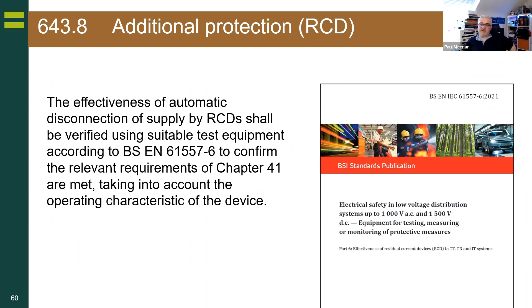And basically what that does is that says the effectiveness of disconnection by RCD shall be verified using test equipment. In our language, it's an MFT or an RCD tester. So just take into account the operating characteristics of the device. Now, regardless of RCD type, effectiveness, and this is the new regulation that's caused controversy, is deemed to have been verified where the RCD disconnects within the time stated below at an AC alternating current test at rated residual operating current of I delta N. So 30 milliamps, it's 300 milliseconds. That's it. As long as it trips at 300 milliseconds, it complies.